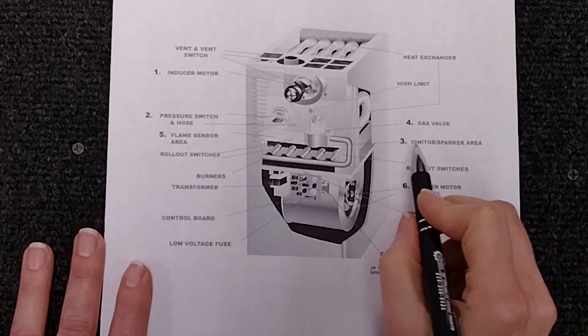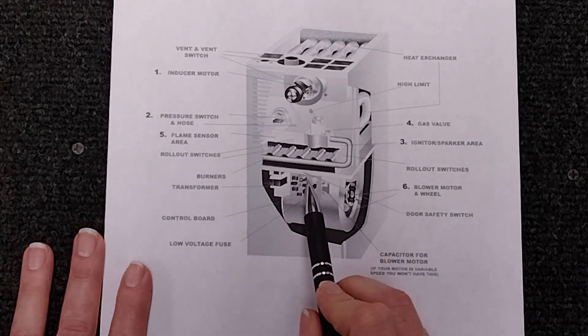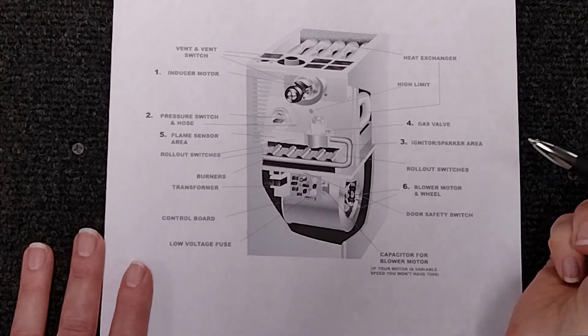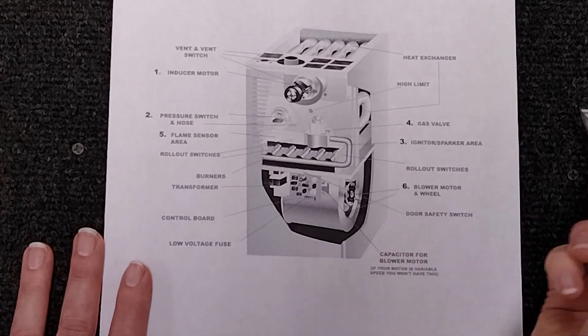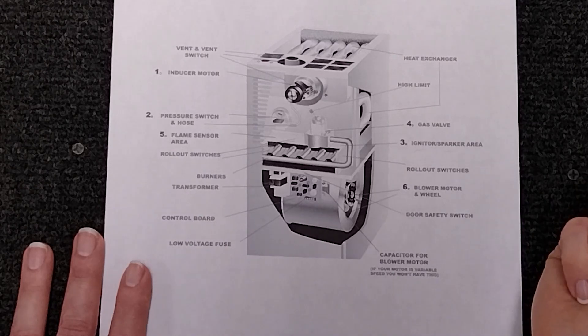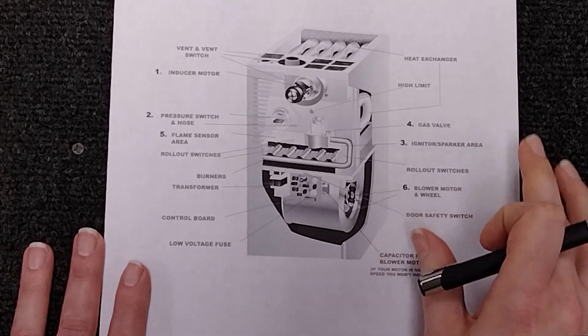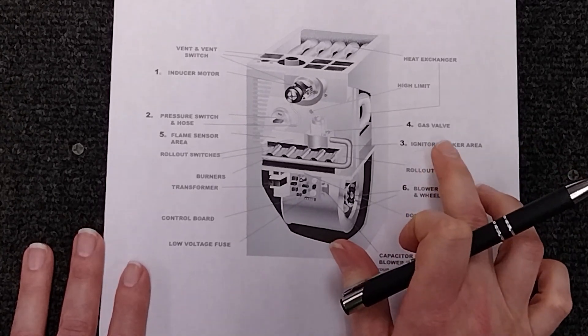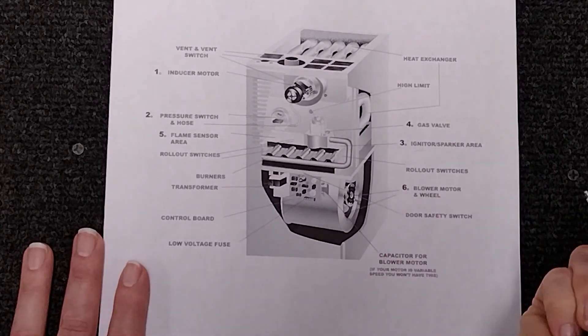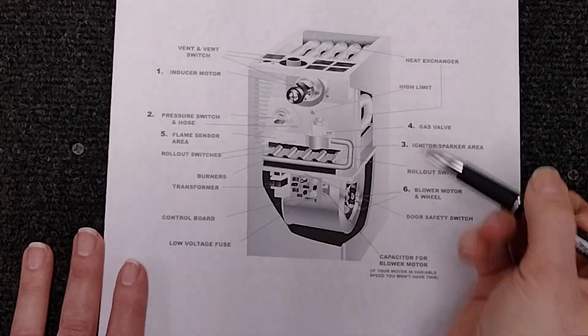Next in line we've got your igniter or sparker if you've got one of those on your board here like this one and once that comes on it's going to stay on for a little bit until it shuts off and once it shuts off the board sends the voltage to your gas valve to open and allow the gas through. Yes you heard me correctly the igniter shuts off before the gas valve goes through and that igniter is burning hot so it's going to still be extremely hot once that gas goes through to ignite.